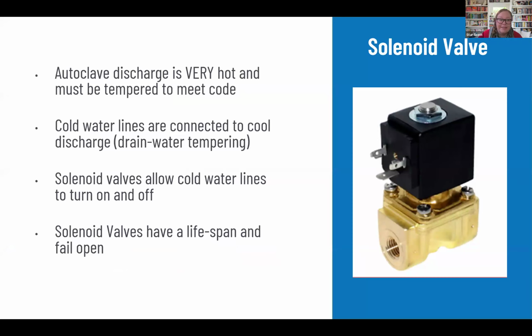So to offset this concern, cold water lines are connected to cool the temperature of the water going down the drain. These cold lines are controlled through a solenoid valve, pictured here, the elusive solenoid valve. But anyway, sometimes, as he mentioned as well, they're called a water miser, and in retrofits, we refer to them as water saving kits. But these valves are amazing. They turn on the cold water when it's needed to cool the hot water discharge from the autoclave.